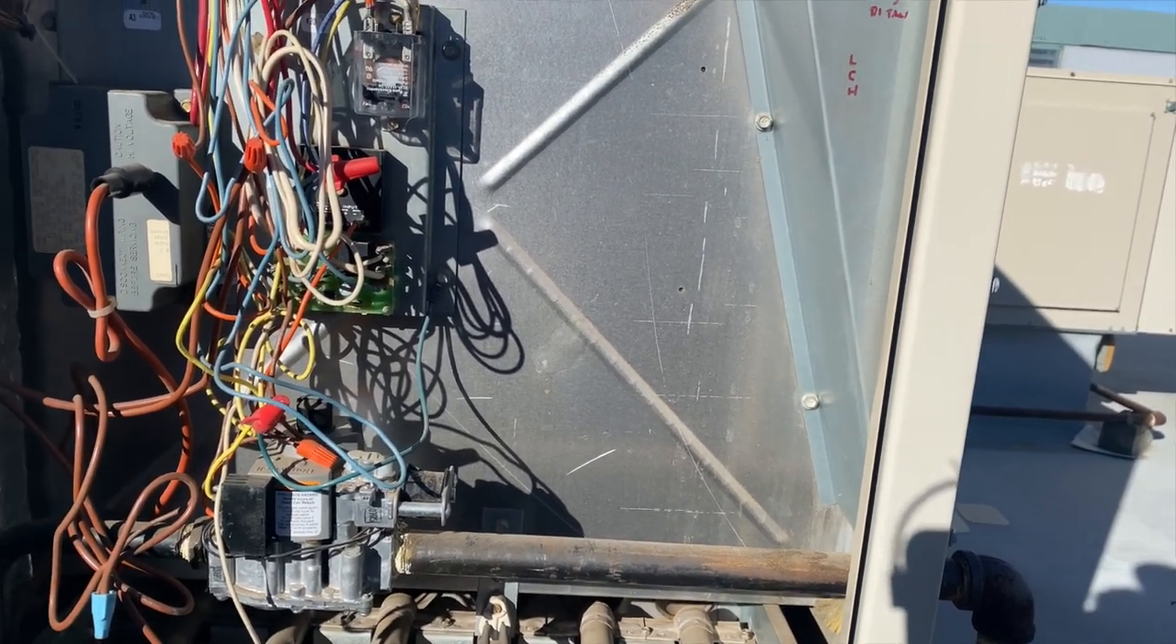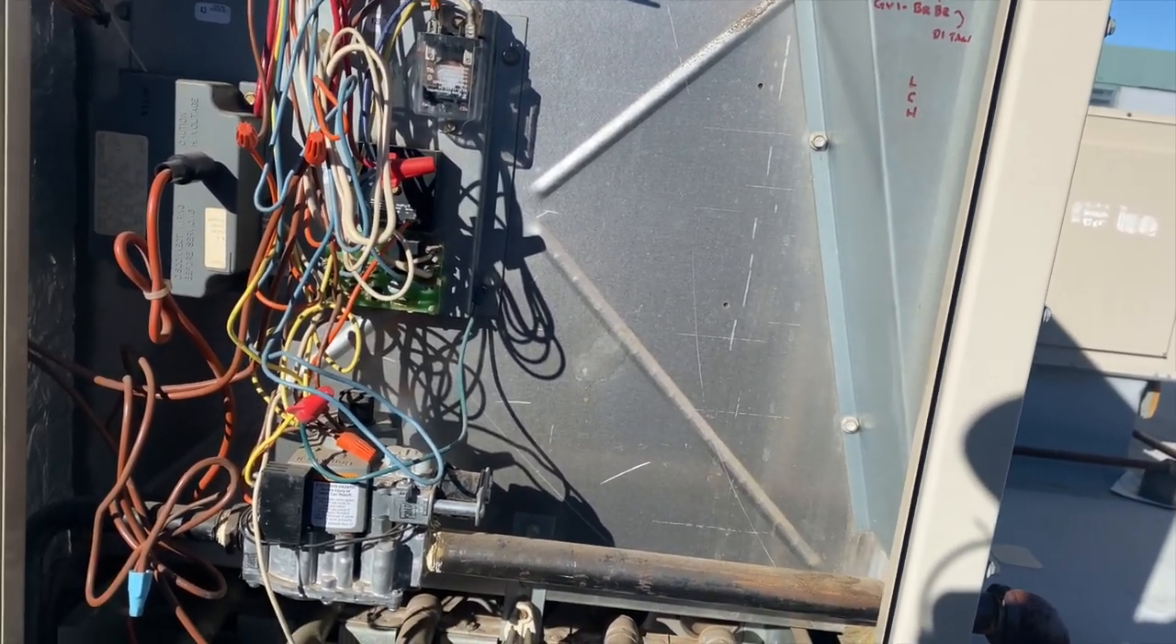I don't see a pressure switch on this so it might have a centrifugal switch. Basically when you spin something, when it spins fast enough it closes a switch, that's called a centrifugal switch. If that's not working or it's stuck, then it thinks that the inducer is not functioning so it won't even try to call for the igniter. We could also have a bad ignition module, so we'll see what's going on.